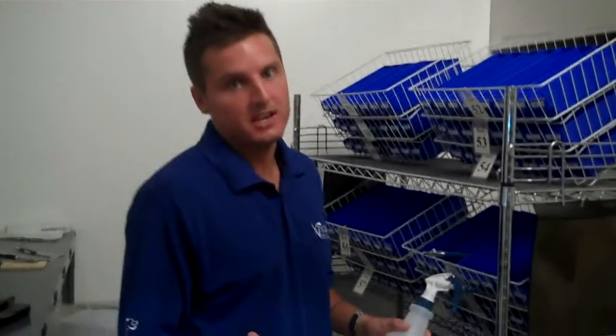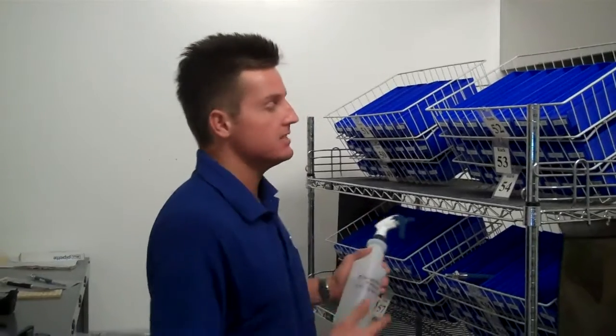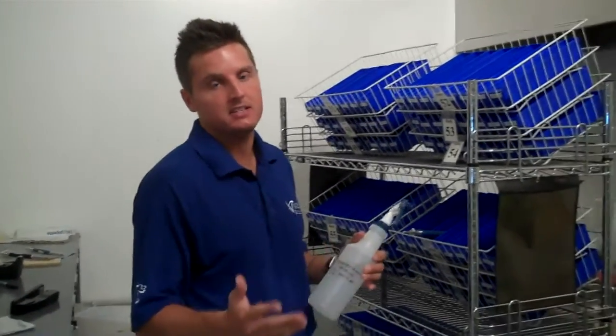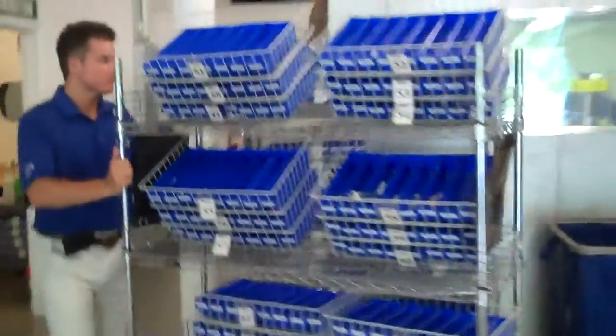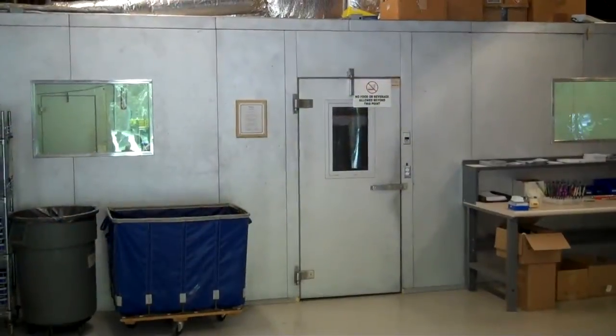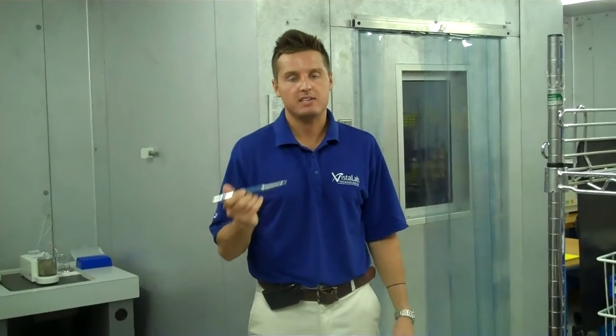So we're now inside the decon room, and the first thing we have to do is spray down all the pipettes with a 70% alcohol solution. Once they're sprayed down, they then sit for 15 minutes. After the decontamination phase is complete, your pipette is ready to be calibrated.